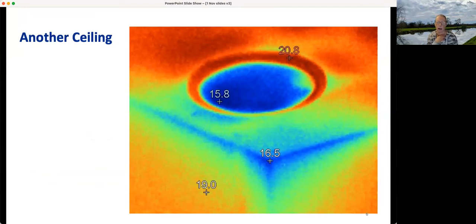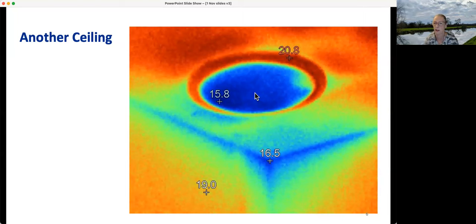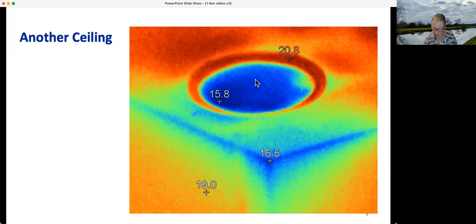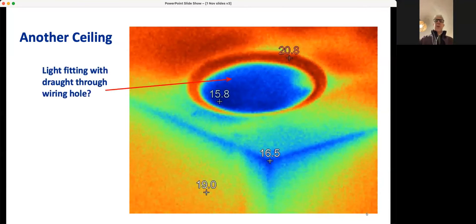Here's another ceiling case. This round thing that looks like a UFO is a downlighter, and you can see clearly it's a bit colder than the rest of the ceiling. The reason is that you're not supposed to insulate over downlighters because of fire risk — so there shouldn't be any rockwool or anything over that. That's probably why.